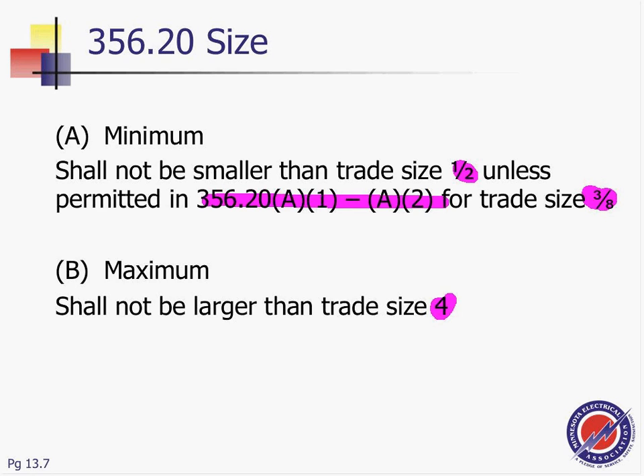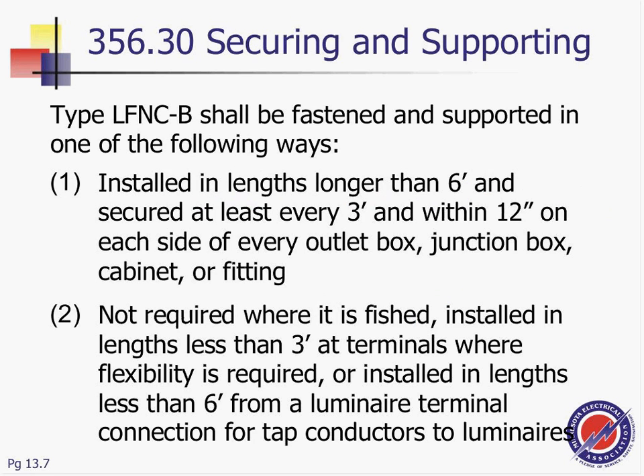I can use it in our application. So, supporting B. Remember that B, that can be installed for more than 6 feet, shall be fastened and supported in one of the following ways. Install the longer length if it's allowed. Remember that one you can install more than 6 feet. Then you have to secure it every 3 feet and within 12 inches of every box, J box or fitting. So only for B, the others can't be installed that way.